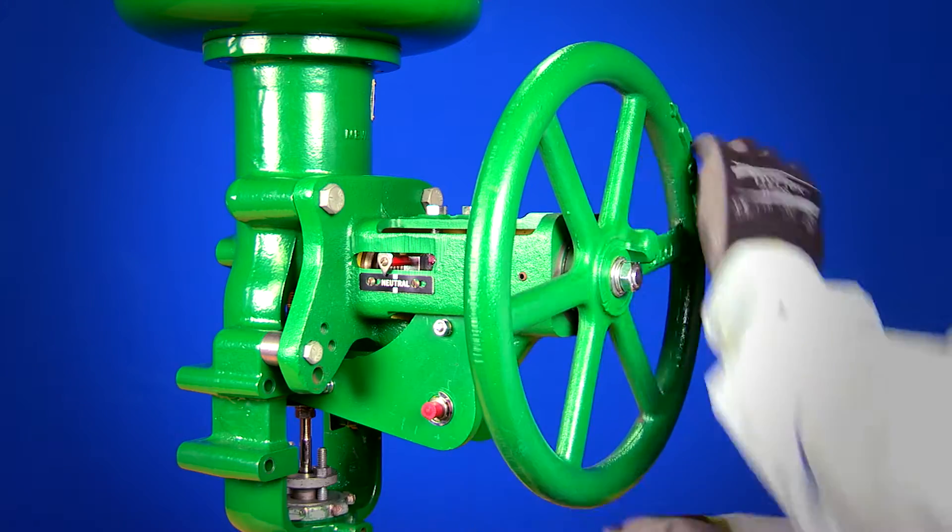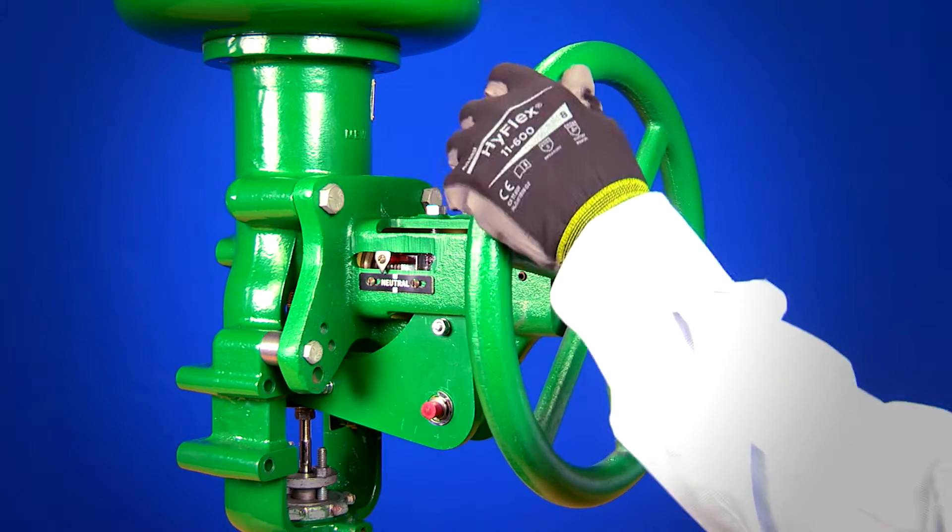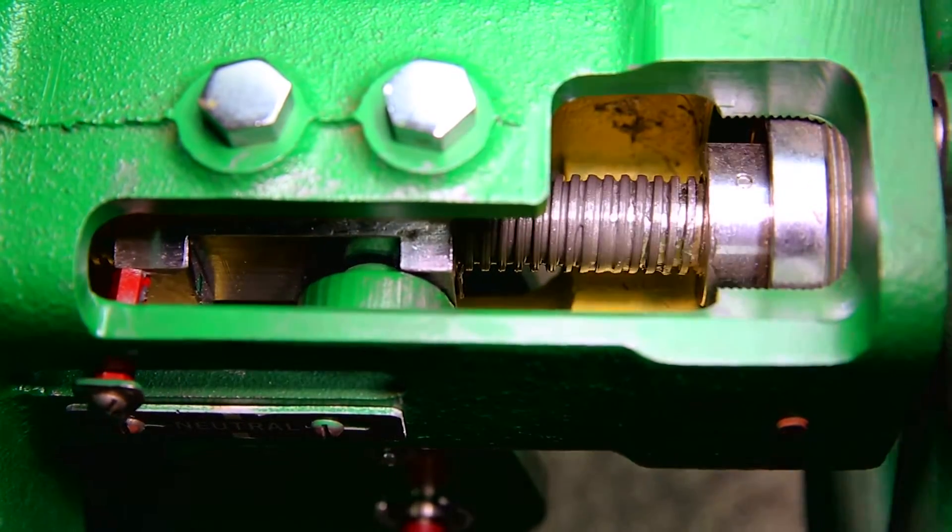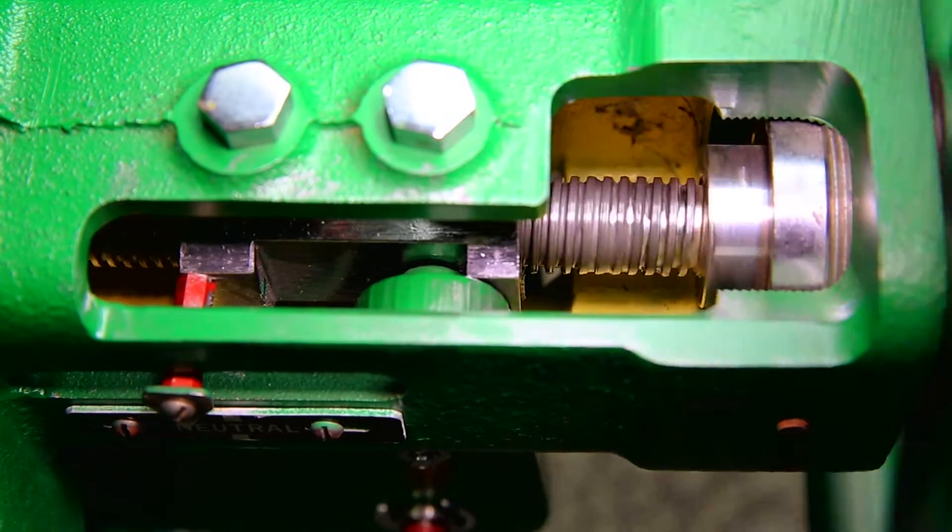The side-mounted handwheel pushes against the force of the actuator spring to move the valve in one direction, and the actuator spring moves the valve in the other direction.